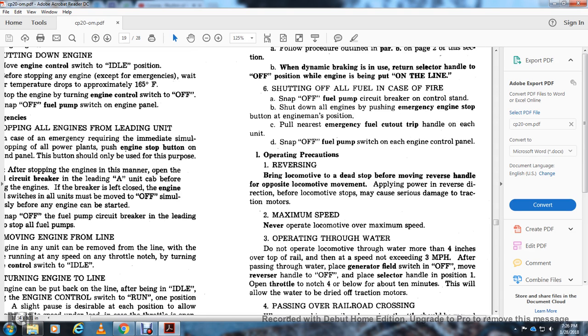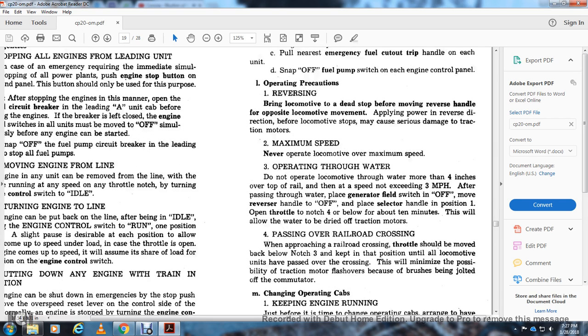3. Operating through water. Do not operate the locomotive through water more than 4 inches above the top of the rail, and at a speed not exceeding 3 miles an hour. After passing through the water, place the generator field switch and the reverser handle in the off position. Place the selector handle in position 1, operating up. Open the throttle to notch 4 or below. Do this for about 10 minutes. This will allow the water to dry off the traction motors.